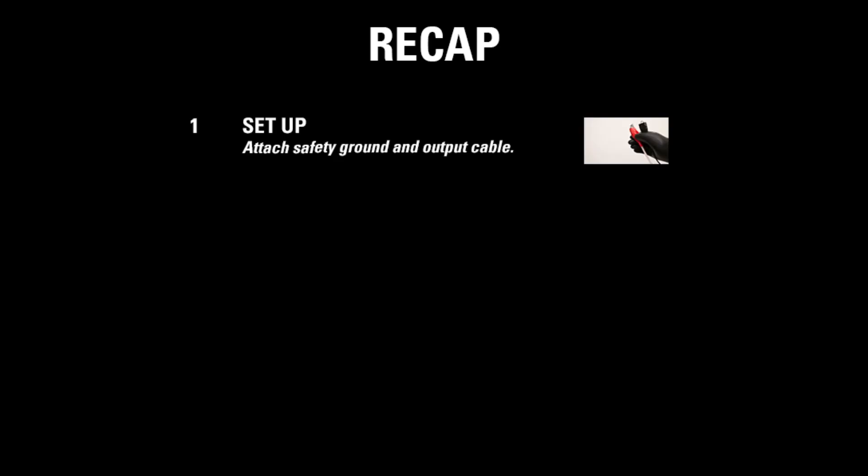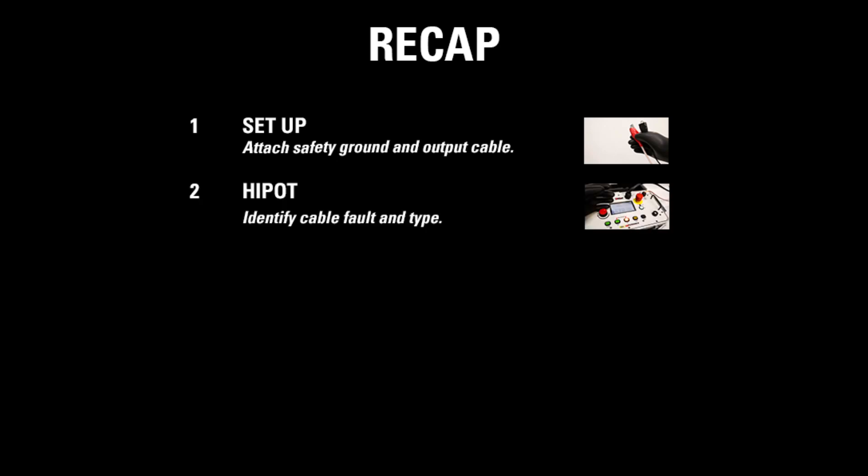To recap, there are five main steps. First, set up the X-Wave — attach the safety ground and the output cable. Then use the hipot mode to identify the cable fault and type.